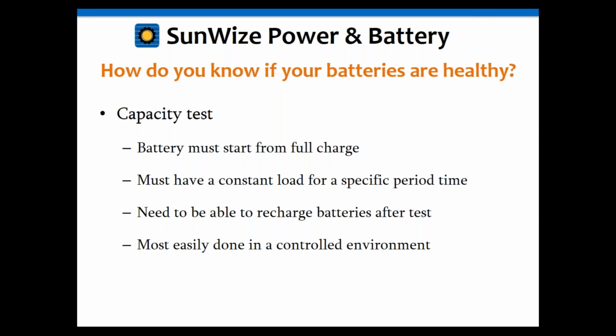Now, if you already have a constant load, that could be as easy as perhaps just turning off the charge to it, the solar array or whatever it is, and then letting it discharge for a specific period of time, and then measuring the batteries along the way to figure out what the capacity is by measuring the voltages. And then based upon that, you can figure out what the battery capacity is to figure out whether the battery is still at 100% capacity or 80% capacity.